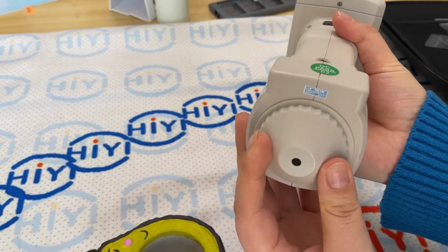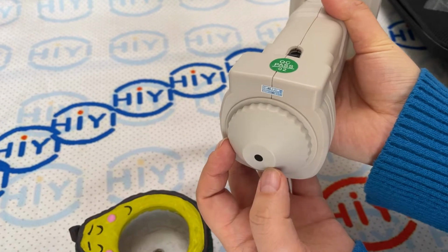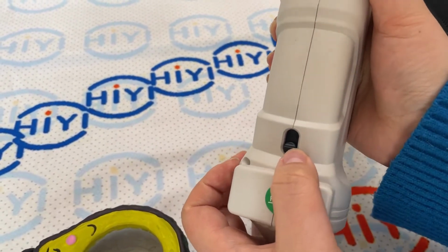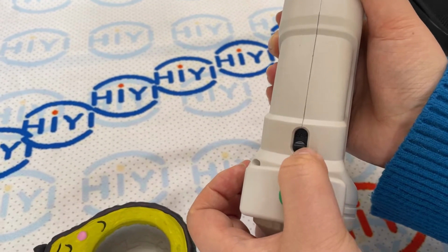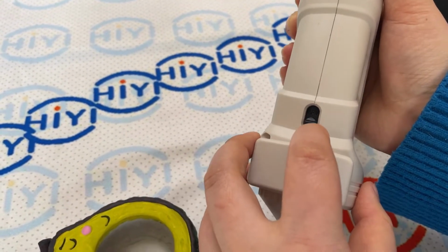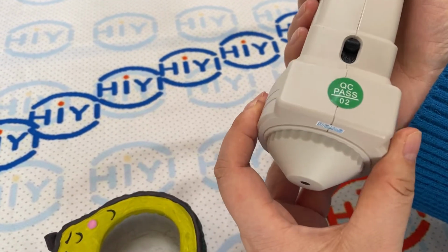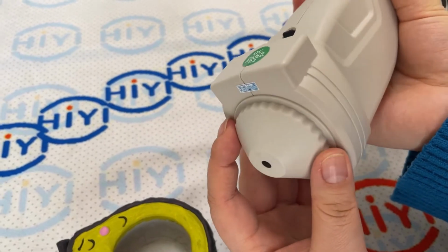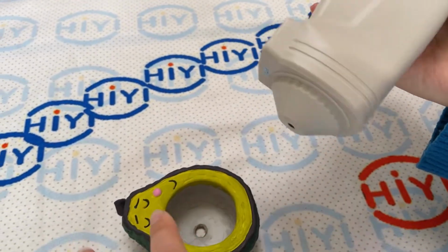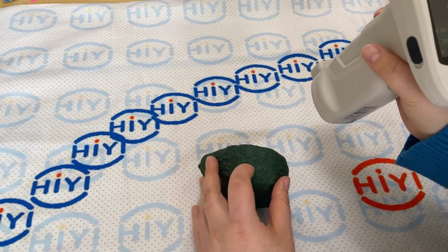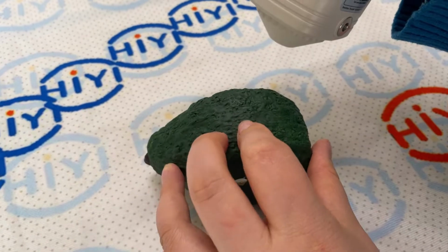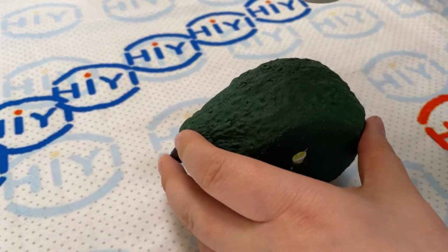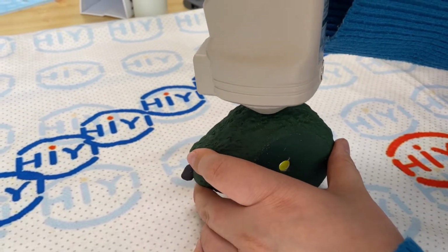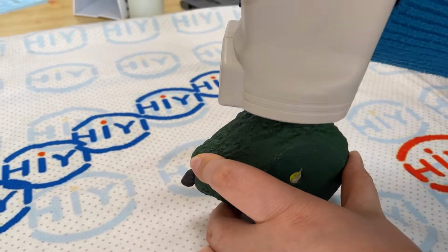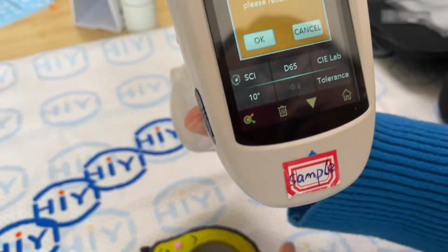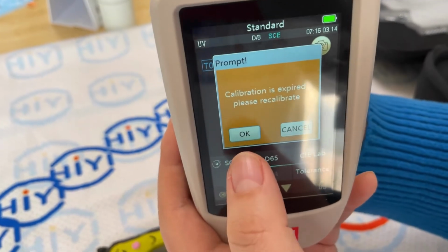The aperture is smaller. We should switch the test mode into SAV mode. Okay, just push the button up. Okay, now we switch to the smaller aperture mode, and now we could test the color of the surface. If we want to test this point, put the aperture on the surface, and then we test. Since we switch the mode, now we need to calibrate.